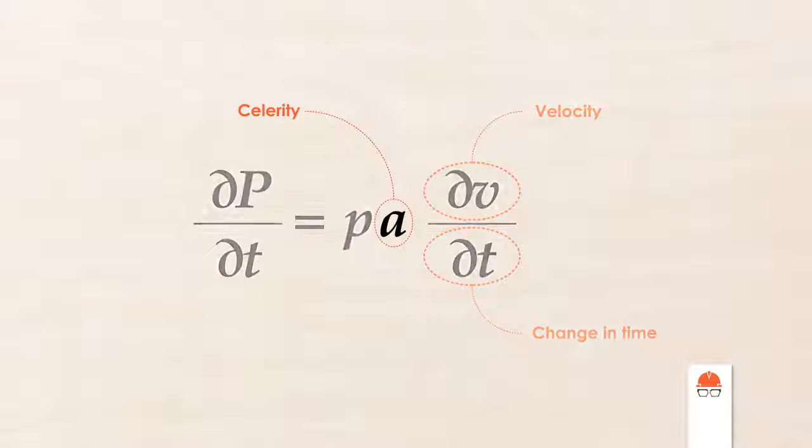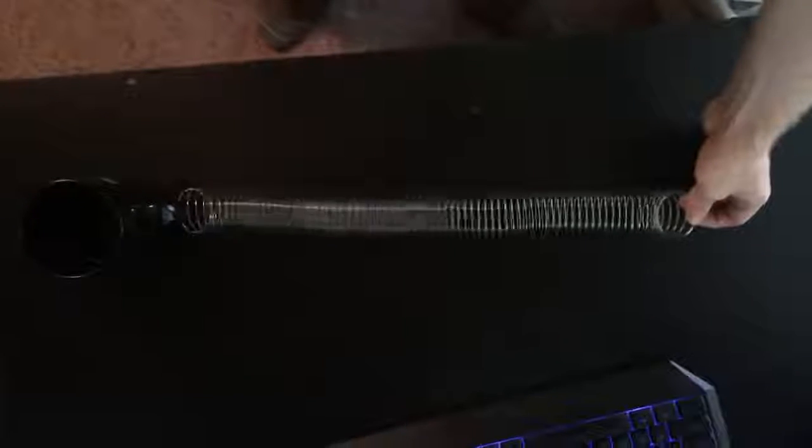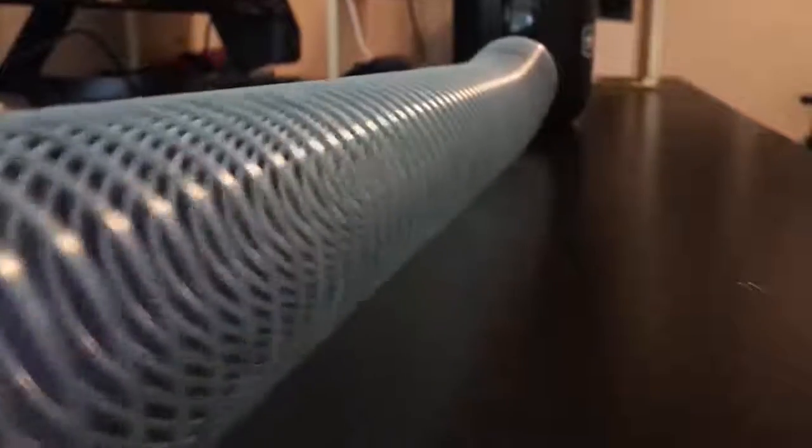The final parameter we can adjust is the speed of sound through the fluid, also known as wave celerity. This describes how quickly a pressure wave can propagate through the pipe. The wave celerity is an indirect measure of the elasticity of the system, and it can depend on compressibility of the fluid, the material of the pipe, and whether or not it's buried in the ground.